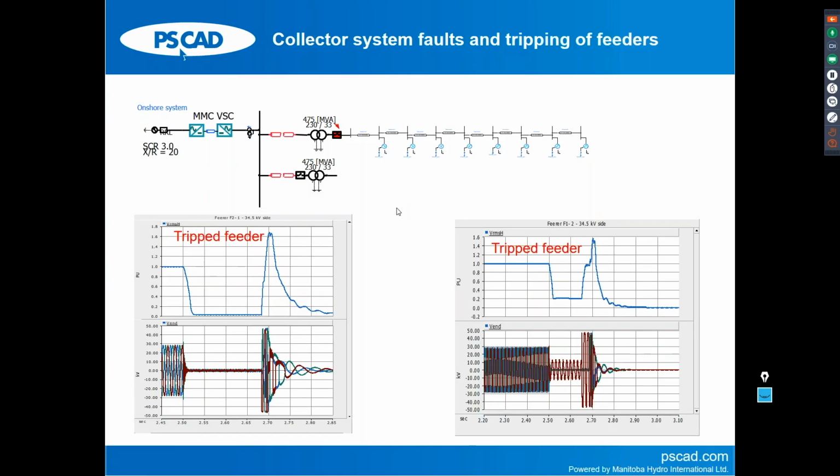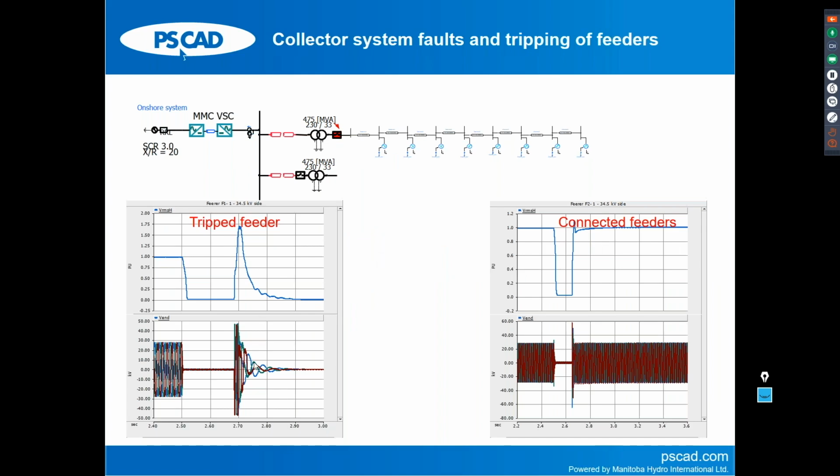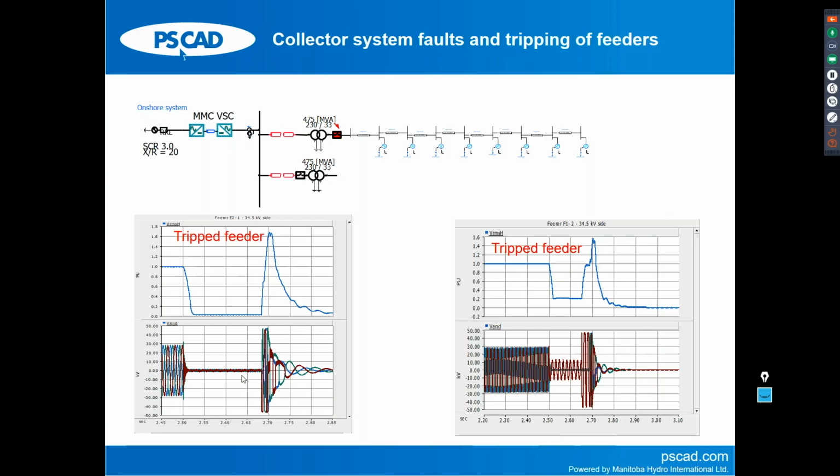So here's another example. In this first example, the voltage seems to come down nicely. In the second example, it may or may not violate. See, it's different. The characteristics are different. This all depends on the fault type, the protection and control strategies adopted by different vendors.